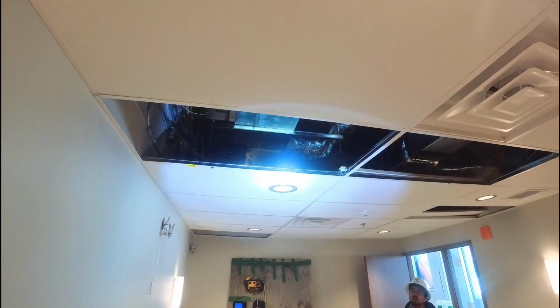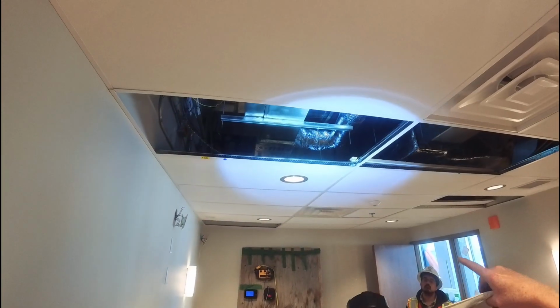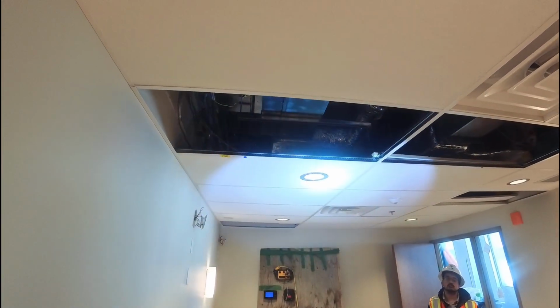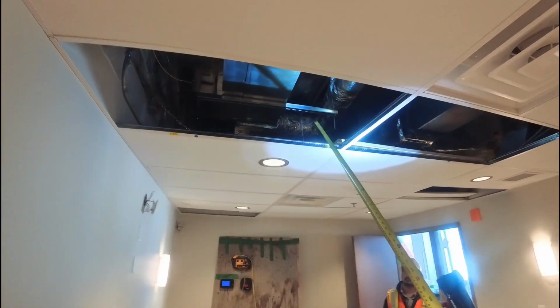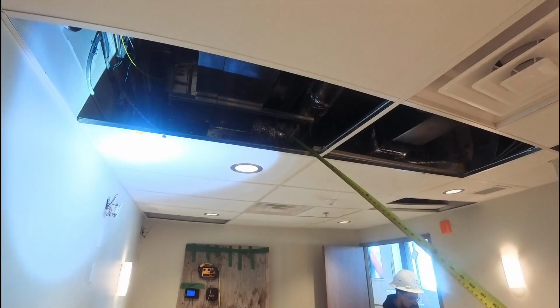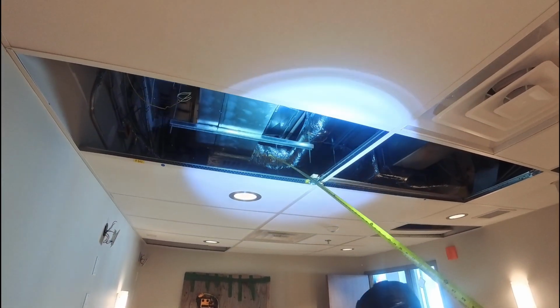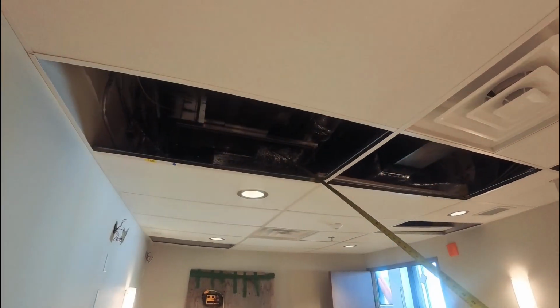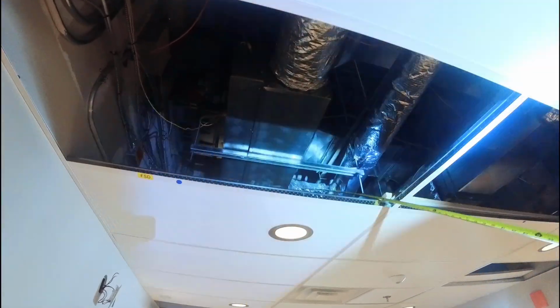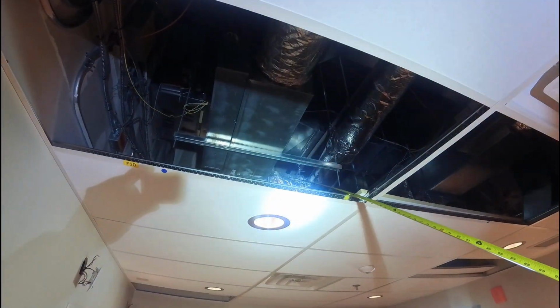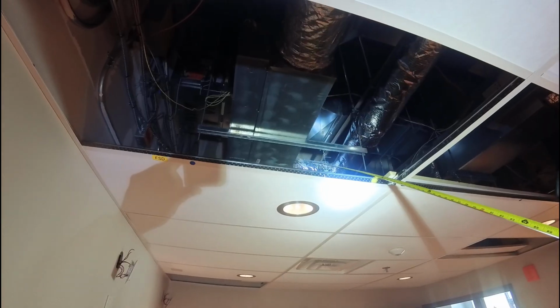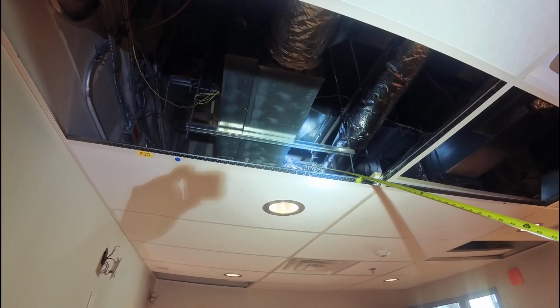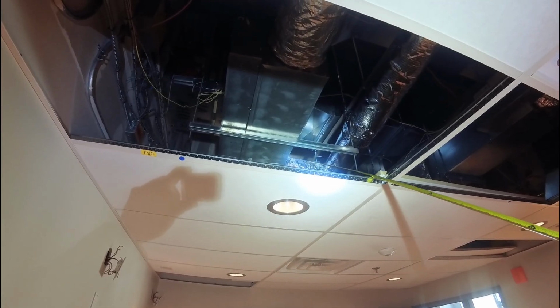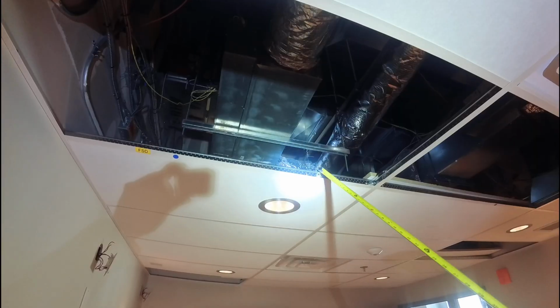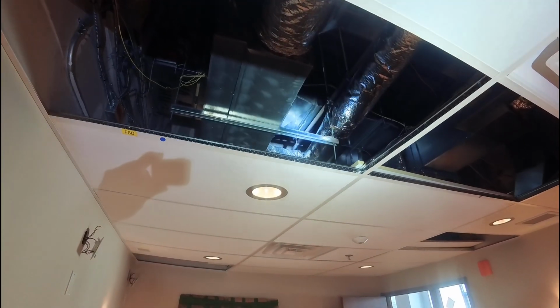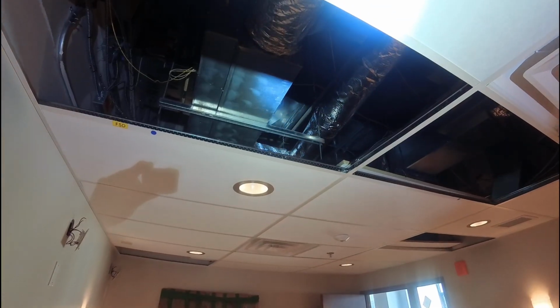Come back far enough. Yeah, there you go. See where it 90s into the side of the duct? I'll point with my tape measure where you can see the handle. Do you see the handle right there? No, I don't. It's right where my tape measure is, buried on the inside. Yeah, there you go, just come back further. See the little tab that's pointed out there? That handle is actually showing direction of airflow as well. The tab is in a parallel position to the run of the duct, which suggests the blade inside is in a parallel position, and the airflow is correct, right? And it's getting all the airflow it needs.